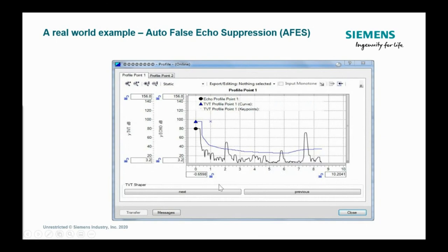Now, one thing I forgot to tell in the story is that the XPS-15 transducer happened to be in a stilling well. As soon as I saw this echo profile, I went, aha, I know exactly what's going on. And I say to the guy, you got a tape measure in your pickup truck? Yeah. I said, go get the tape measure and let's open up the wet well, take a look. The key is 7 feet down, I got an echo off of something. I'm in a stilling well. Exactly 10 feet later, here's another echo.